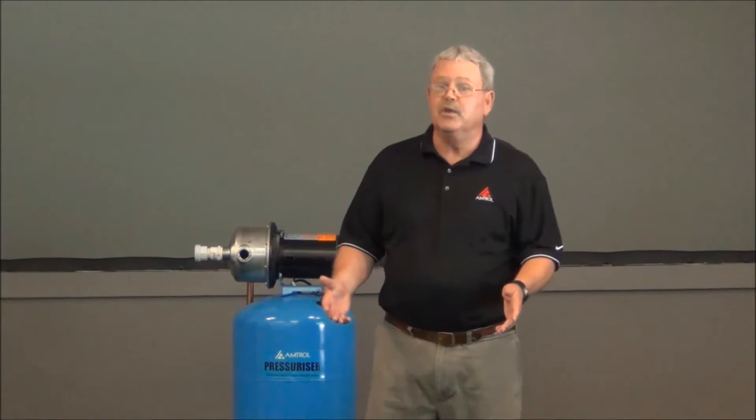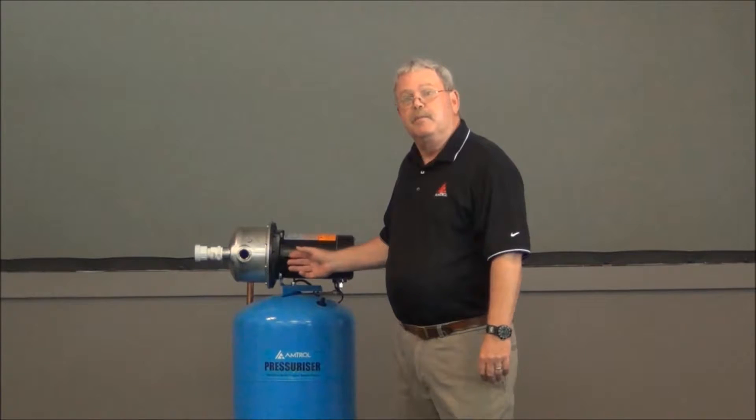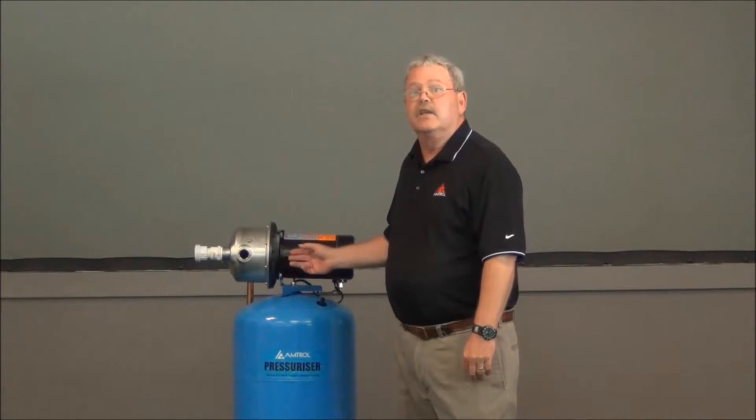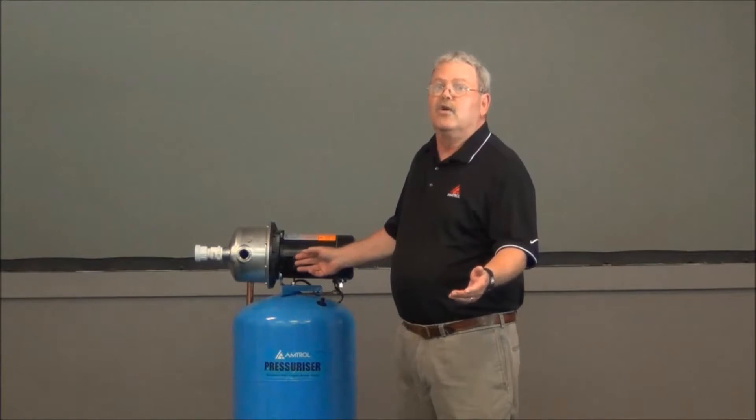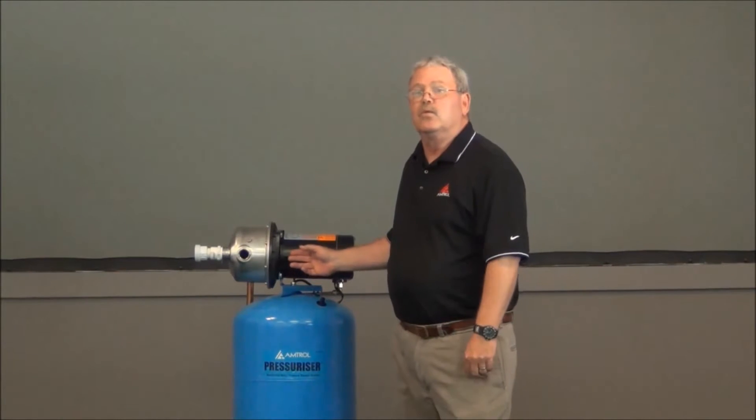And if you have low voltage, what happens is this pump is going to see the low voltage, it's going to overheat, and it's going to do the same thing. It's going to go off on thermal overload and then it will restart once it cools down.